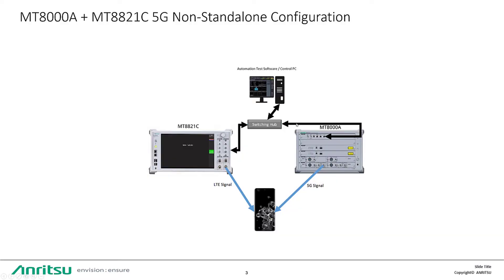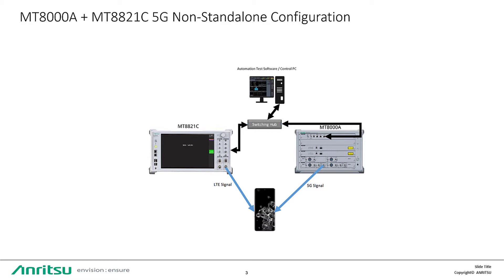MT-8000A and MT-8821C 5G non-standalone configuration. On the top, we have our control PC, which will also house our automation test software ATS. The control PC drives the MT-8000A as well as the MT-8821C. All are connected via IP address with a network hub or a switch.